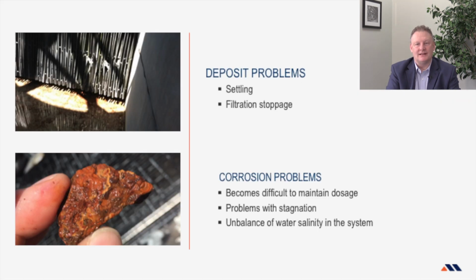Water quality imbalance is also an issue with seasonal or sudden stoppages. These typical problems are, with no water circulation, there's a potential for silt and debris to settle in the system. In some instances, the side stream filtration also stops. Corrosion is accelerated due to insufficient inhibitor. Other problems might arise with the circulation dynamics as the buildup of biofilm and Legionella growth.